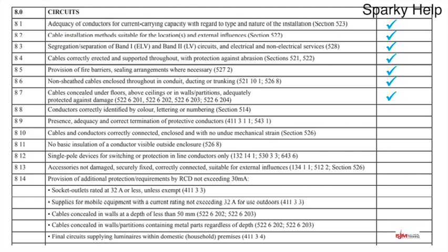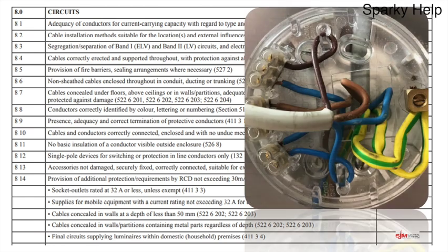Conductors correctly identified by colour, lettering, or number. On this three-plate ceiling rose we can see neutrals on the bottom, the earths, and the loops in the middle which is the three-plate part. But we can see another blue which would be the switch line going to the brown of the flex, and it has no sleeving on — so that would be a fail. Likewise for two-way switching using three core and earth, the black and grey cores need to be sleeved brown, and for three phase all the same-colour conductors need to be labelled L1, L2, and L3.